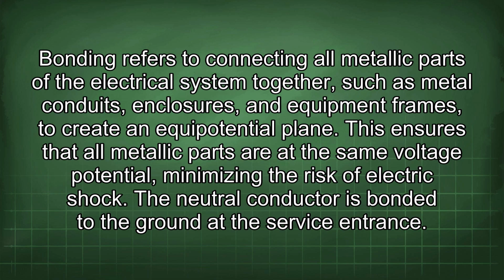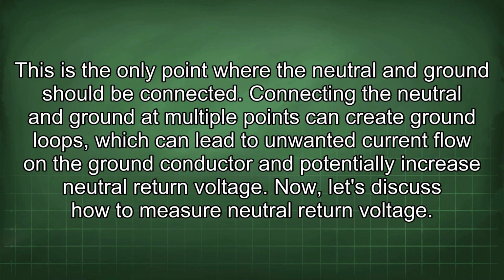The neutral conductor is bonded to the ground at the service entrance. This is the only point where the neutral and ground should be connected. Connecting the neutral and ground at multiple points can create ground loops, which can lead to unwanted current flow on the ground conductor and potentially increase neutral return voltage.